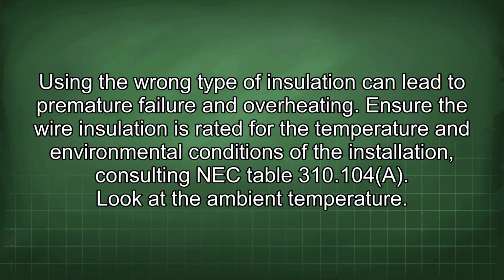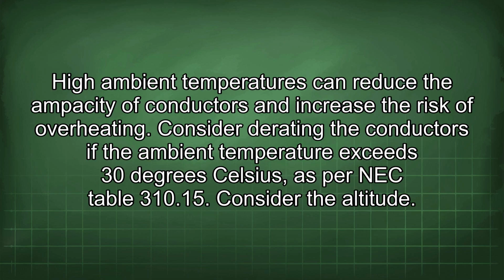Using the wrong type of insulation can lead to premature failure and overheating. Ensure the wire insulation is rated for the temperature and environmental conditions of the installation, consulting NEC Table 310.104(A). Look at the ambient temperature. High ambient temperatures can reduce the ampacity of conductors and increase the risk of overheating. Consider derating the conductors if the ambient temperature exceeds 30 degrees Celsius as per NEC Table 310.15.